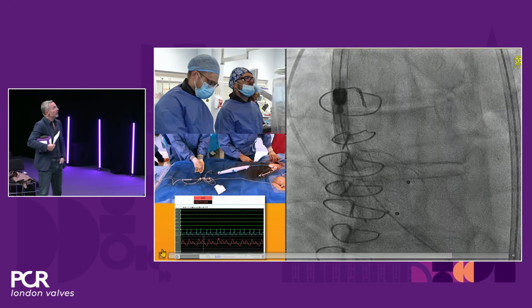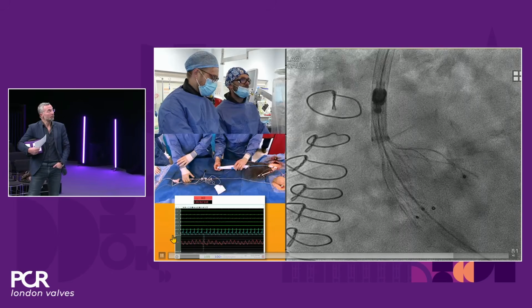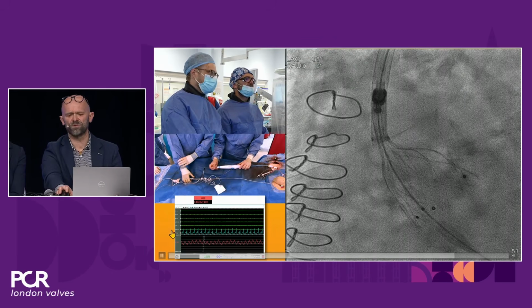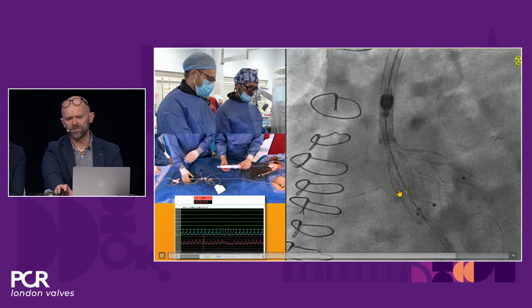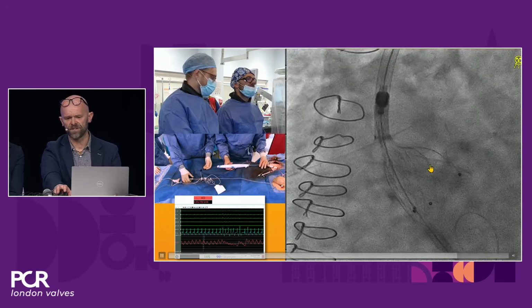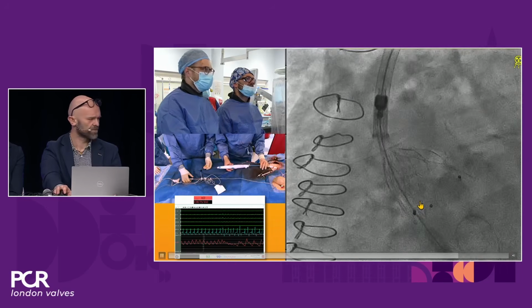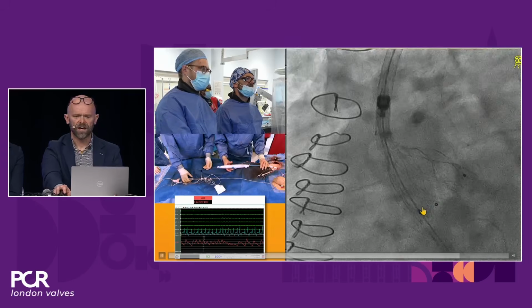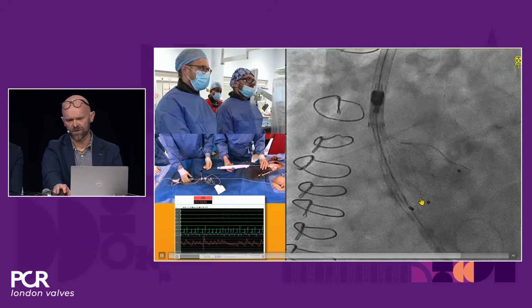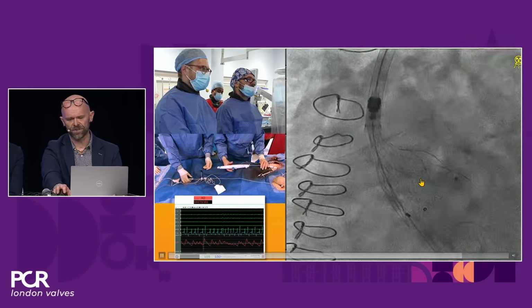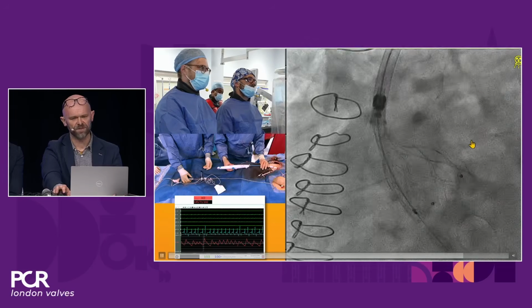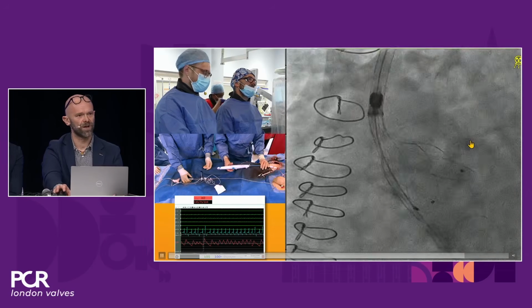So we did the echo. You've seen it before. There were no gradients, no AR, kind of trace AR, let's say. And I normally take the pigtail out for final release. Pull on the wire, so release the tension from the system, so there's no tension in the system. And you can appreciate as well here, now with this kind of release recording, we release the valve. The valve is expanded much nicer than in the first few openings.